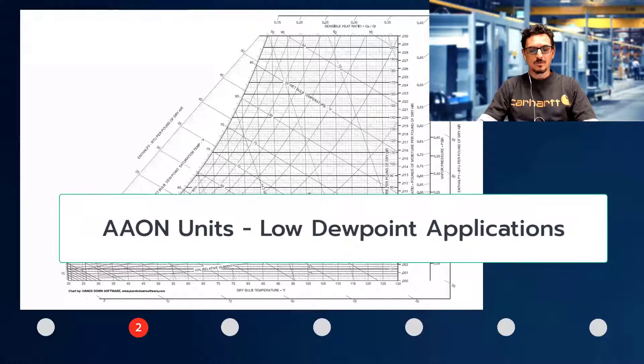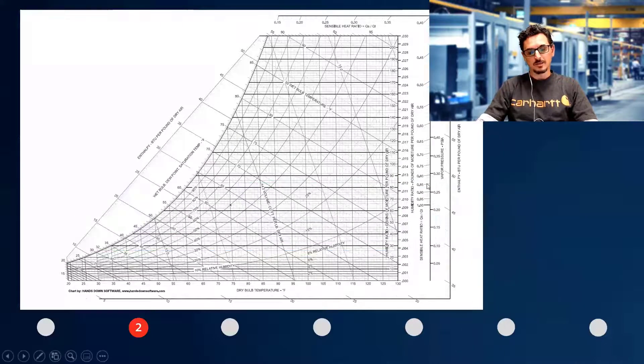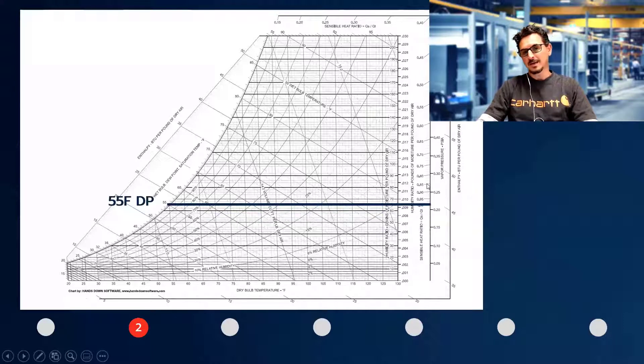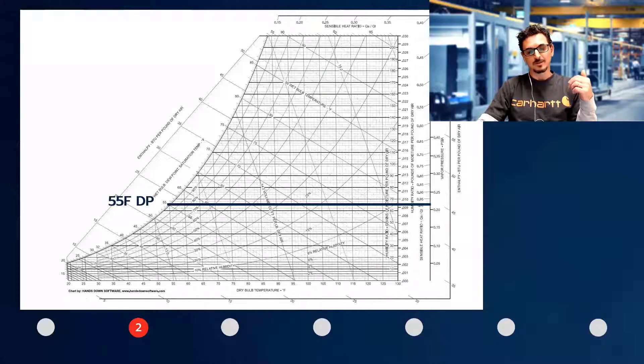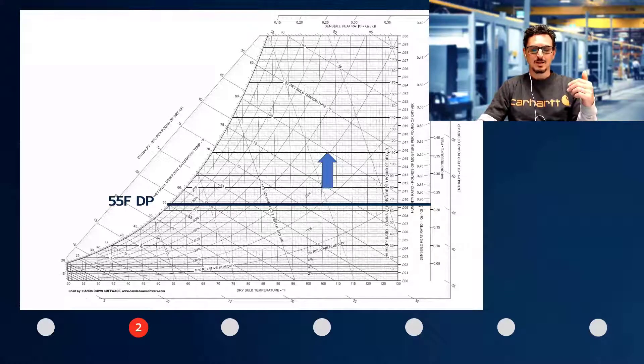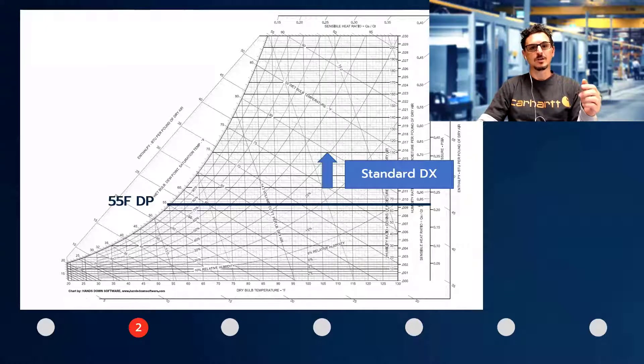So what do we mean by low dew point? We'll take a look at this psychrometric chart here. Personally, I cut off low dew point at 55 degrees — that's the space design conditions. Anything above 55 degree dew point, standard DX equipment will get you there most of the time.